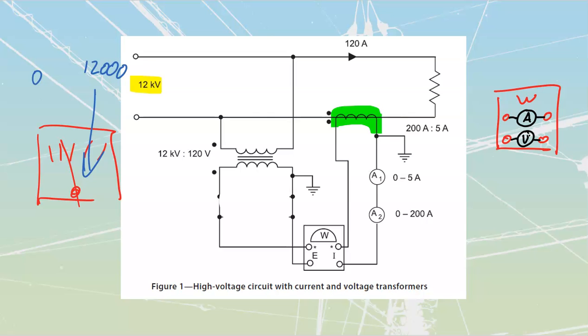But in this case, what they have done is they have changed where that meter actually is. My voltmeter is across here. My ammeter is across here. You need to be able to read that from the drawing. You should go and draw those little metering sections in, and then that is going to help you to interpret the rest of the diagram. If I take a look at this now, you can see that from my 120 volts, I'm going through my metering section and back up. It's really no different than any of those other meters that we saw inside of the section there. We're just connecting to the voltage section of our watt meter.